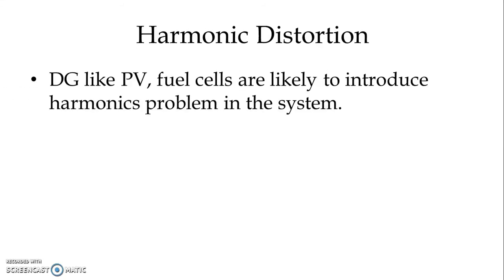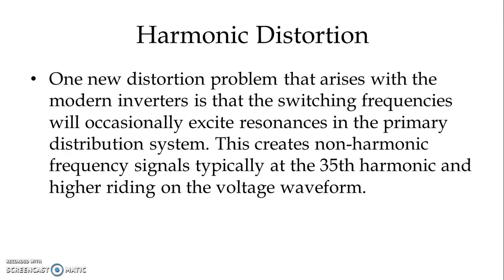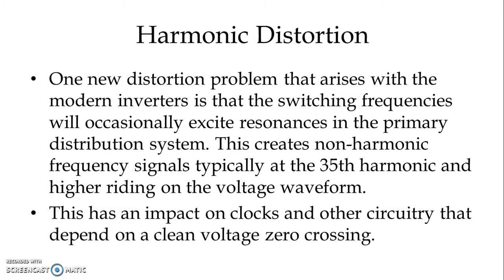Distributed generators like photovoltaic and fuel cells are likely to introduce harmonic problems in the system. Harmonics from distributed generators come from the inverters and some synchronous machines. One new distortion problem that arises with modern inverters is that the switching frequencies will occasionally excite resonance in the primary distribution system. This creates non-harmonic frequency signals, typically at the 35th harmonic and higher, riding on the voltage waveform, which has an impact on clocks and other circuitry that depends on a clean voltage zero crossing.